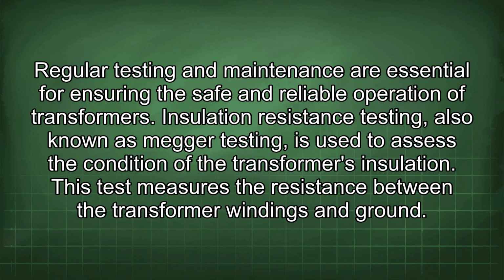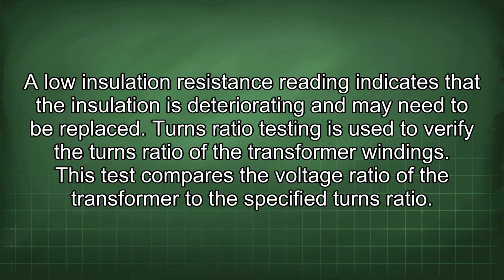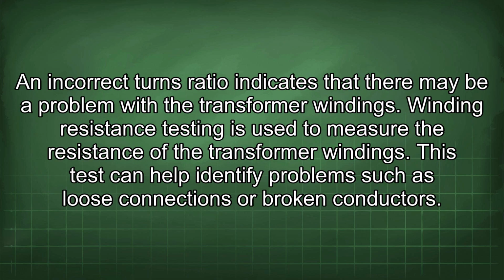Regular testing and maintenance are essential for ensuring the safe and reliable operation of transformers. Insulation resistance testing, also known as megger testing, is used to assess the condition of the transformer's insulation. This test measures the resistance between the transformer windings and ground. A low insulation resistance reading indicates that the insulation is deteriorating and may need to be replaced. Turns ratio testing is used to verify the turns ratio of the transformer windings. This test compares the voltage ratio of the transformer to the specified turns ratio. An incorrect turns ratio indicates that there may be a problem with the transformer windings.